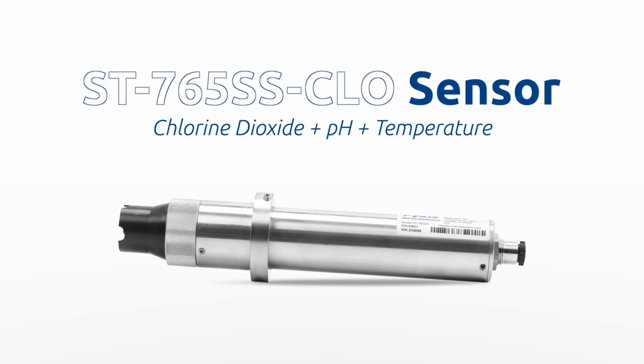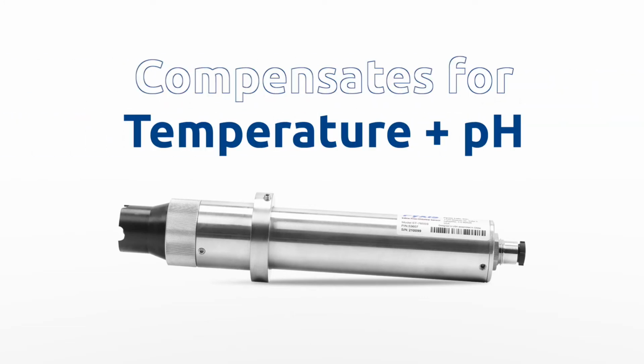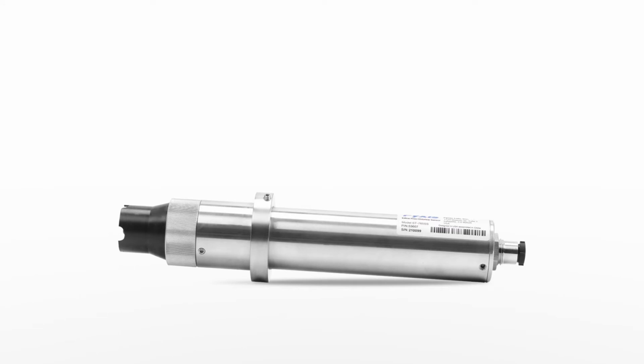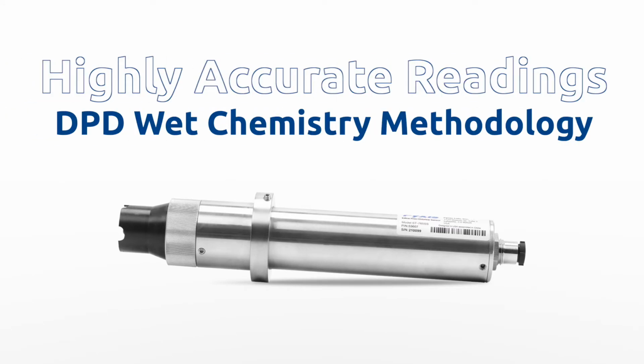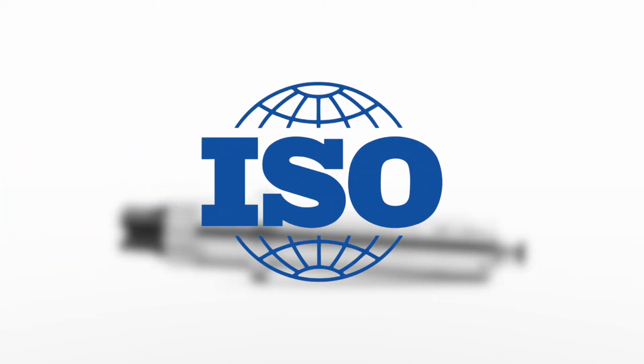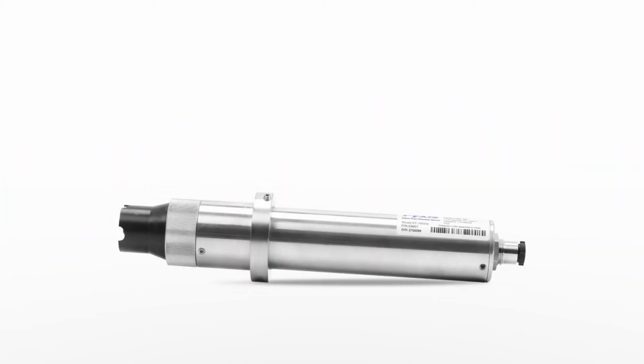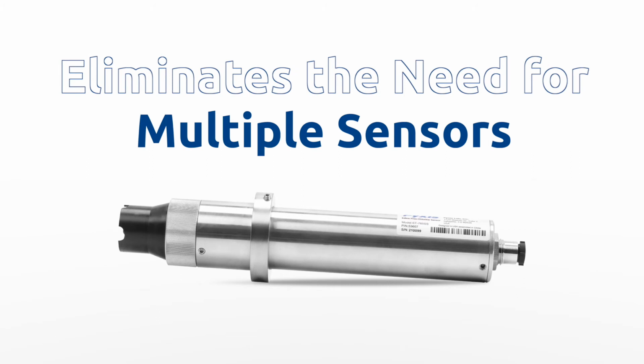and temperature. Both can perform temperature and pH compensation for the measurement of free chlorine or chlorine dioxide based on real-time conditions present in the application of use. These unique internal compensation algorithms result in highly accurate oxidizer measurement consistent with DPD wet chemistry methodology as high as a pH of 9.0 and is compliant with US EPA 334.0 and ISO 7393 guidelines. The fully integrated compensation and measurement capability of the ST765SS eliminates the need for the purchase and use of multiple sensors and a controller for pH-compensated oxidizer detection.